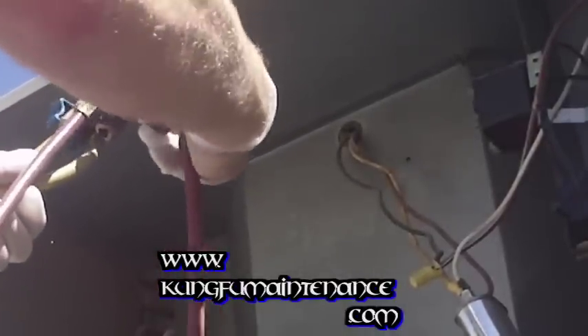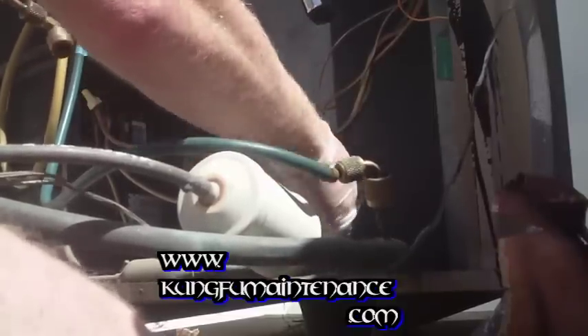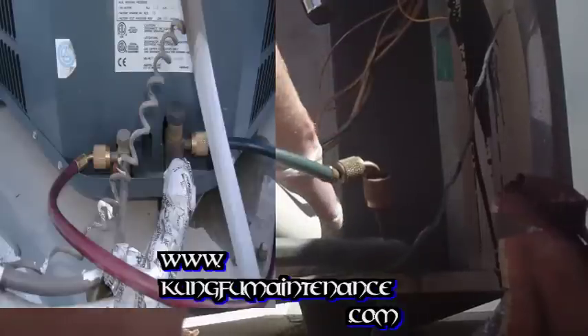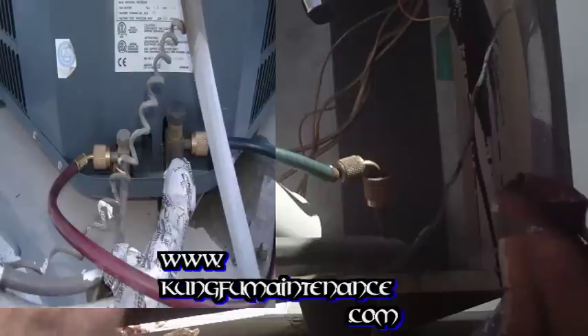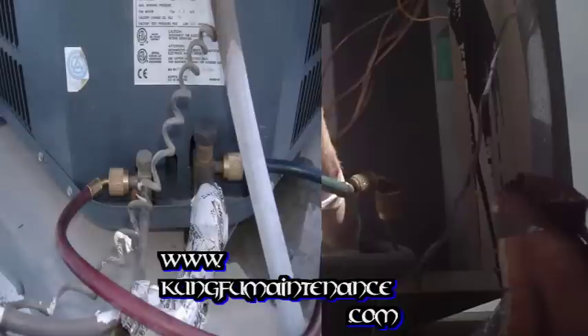This is the high side line right here with the Schrader valve cap. Listening for any hissing or anything coming out there, and also looking for any oily residue spots that would indicate that we have a leak there. So I'm going to hook up my high side line.